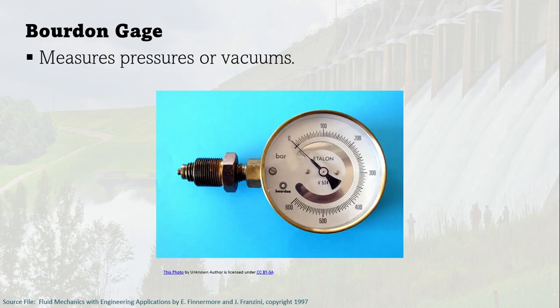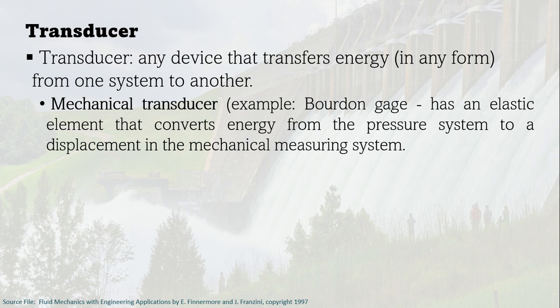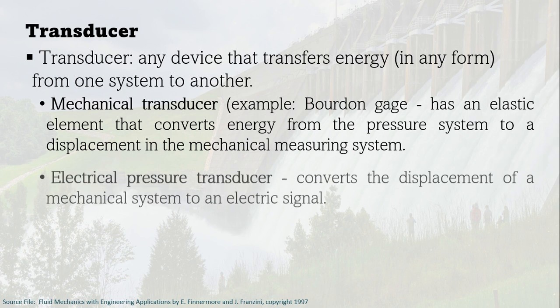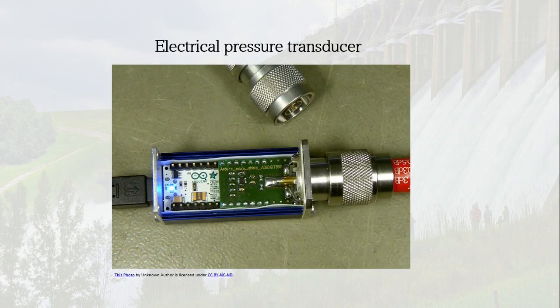Another measuring instrument for pressure is the Bourdon gauge, which is used to measure pressures or vacuums. We also have a transducer — any device that transfers energy from one system to another to indicate pressure changes. The Bourdon gauge is an example of a mechanical transducer because it has an elastic element that converts energy from a pressure system to a displacement in a mechanical measuring system. We also have electrical pressure transducers, which convert the displacement of a mechanical system to an electrical signal to measure pressure.